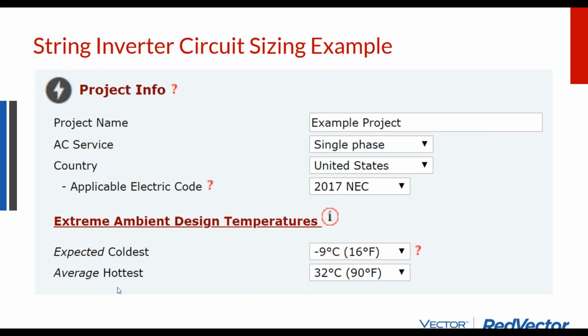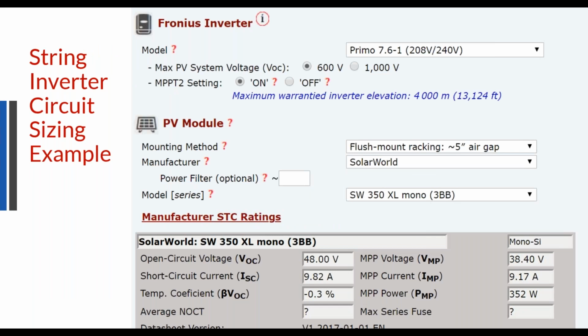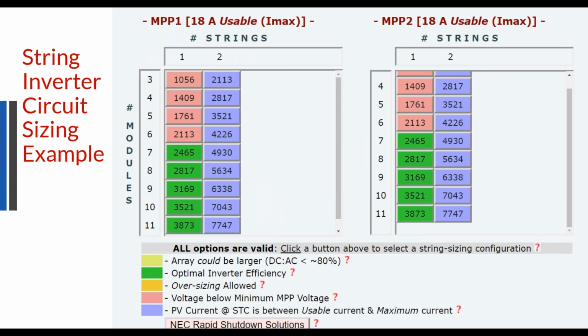making sure that your system stays below, well, if it's a residential project and it's on a building, making sure your system stays below 600 volts. And so your design software is taking in the temperature correction factor of the solar panel itself and making sure your circuits stay below 600 volts. And so you put in what inverter you're using and what solar panel you're using, and it essentially tells you how many solar panels you can have on a circuit based on those temperature correction factors. That's pretty common to any solar design software.